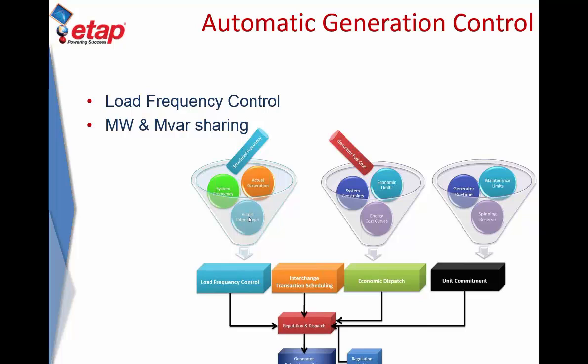A lot of industrial plants which can operate as microgrids tend to operate with net zero power, which implies that the interchange values or the power flows are maintained close to 0 megawatt. The utility is there for reliability purposes.